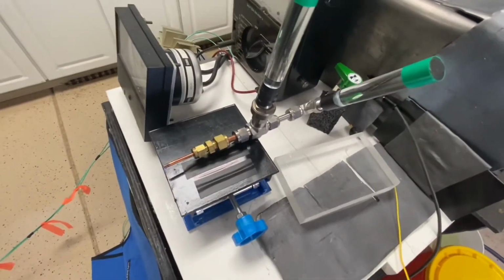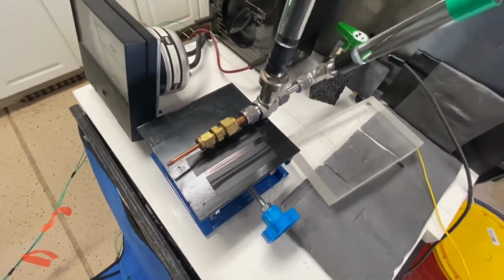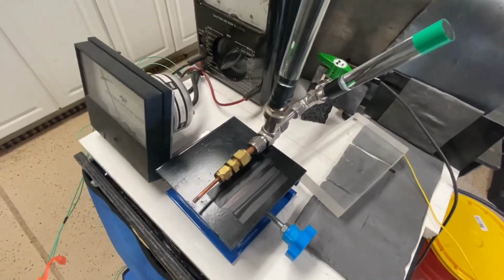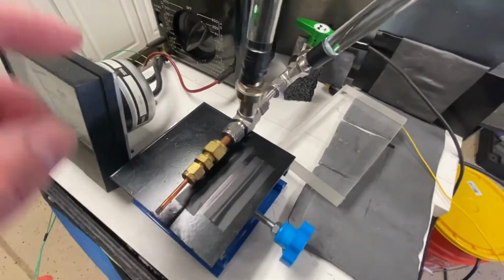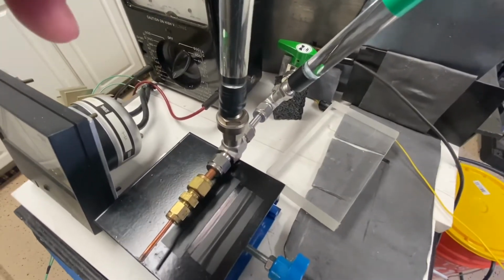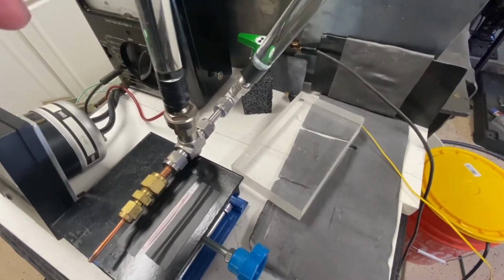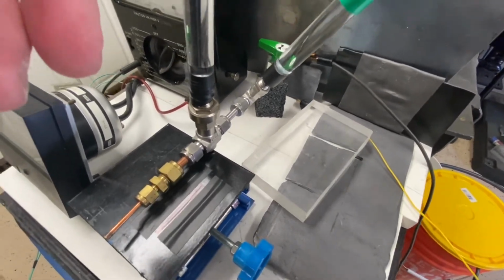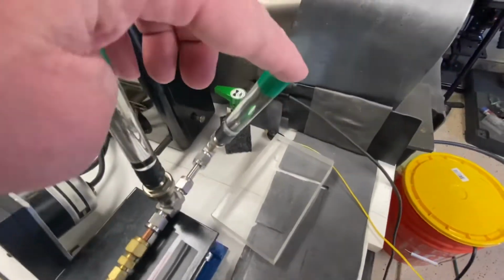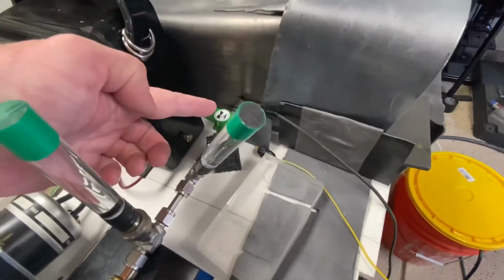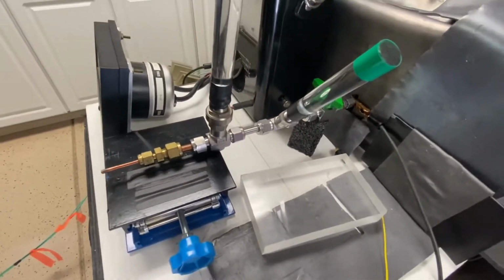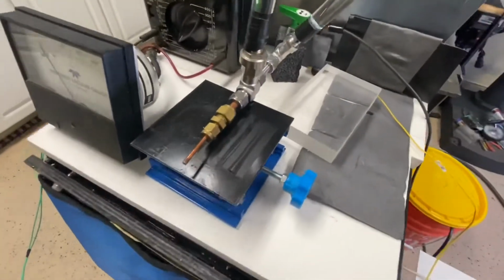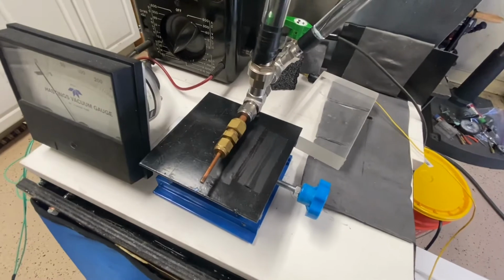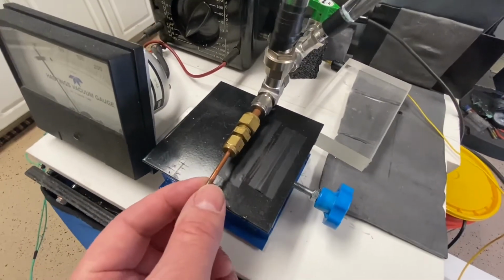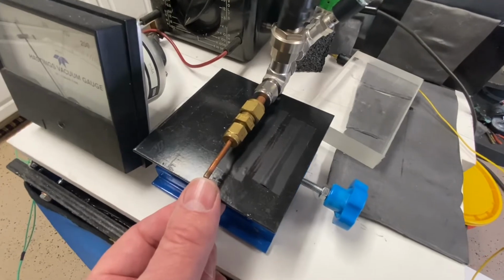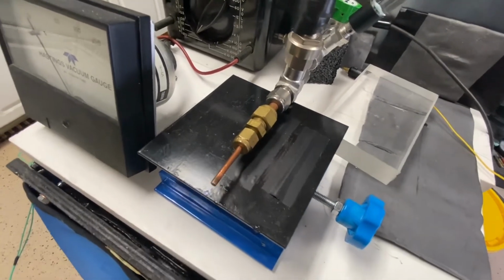Okay, shown here is the valving system for the deuterium input. Deuterium from a 100 milliliter syringe is fed in here. This is a SS-SS4 needle valve. I'm sorry, I got this backwards. So this is a medium flow valve. This is an SS-SS4 valve. And here's just a gate valve for turning off the entire gas flow system. Gas from the syringe is fed directly into this point here through a small 2 millimeter silicone tube.